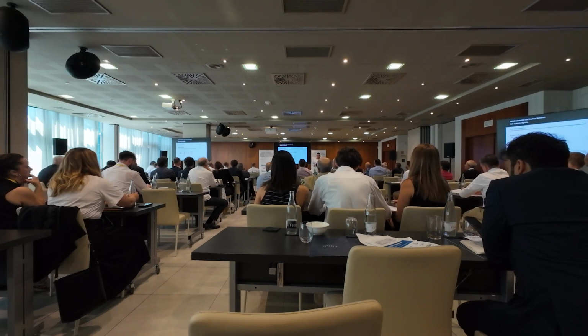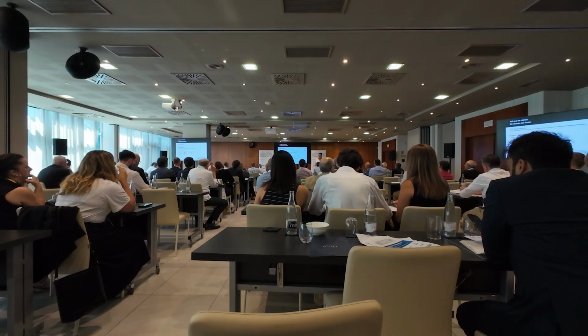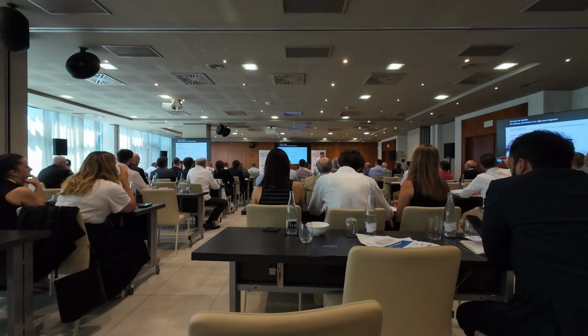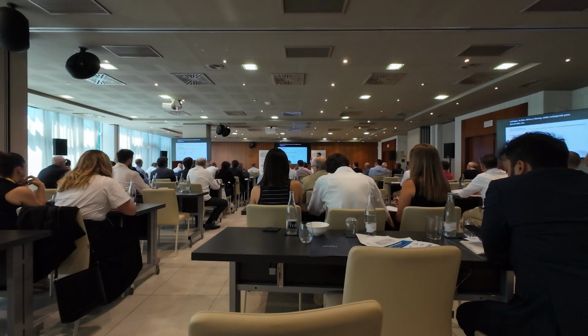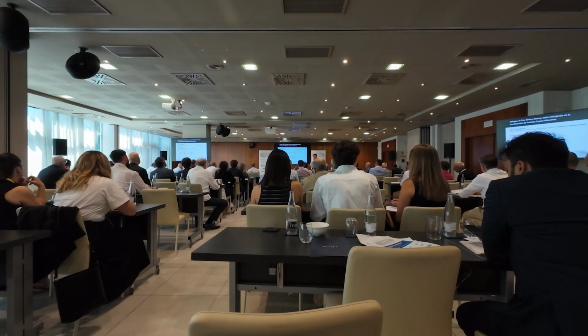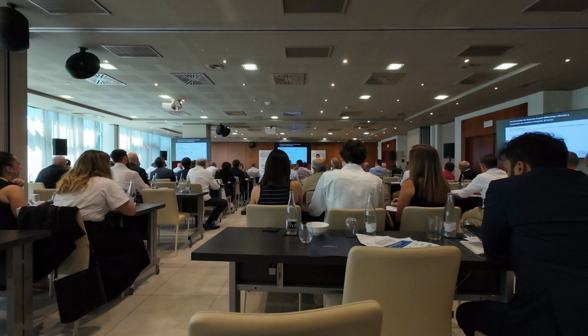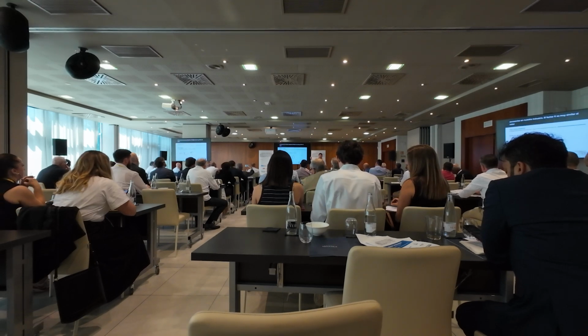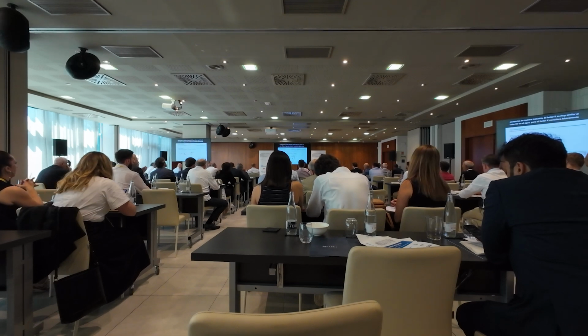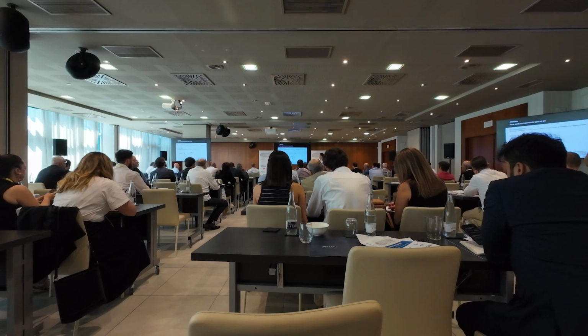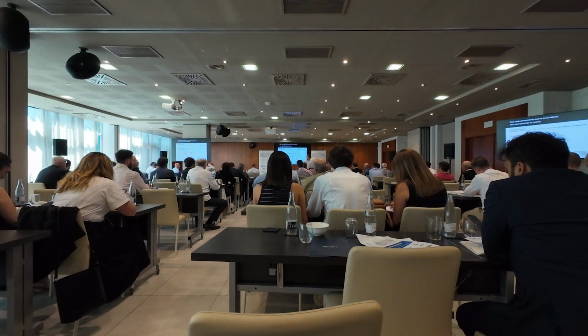The K-factor method is something some of our colleagues, Dr. Elvira and Danny, are working on, building out K-factors for different valves and fittings in our industry. The K-factor is very similar to the Cv value in water, but the K-factor basically considers the friction and the effective length for each component that goes in the pipe, but still taking into account the length and diameter and then the velocity through.